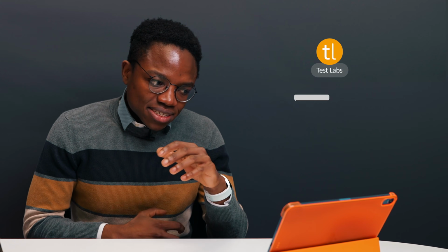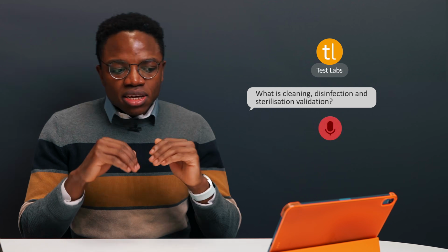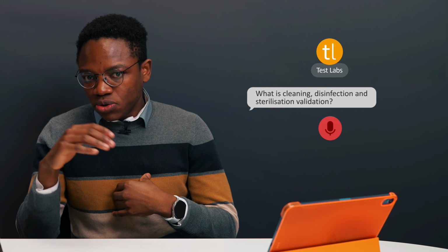The next question I get quite a lot from manufacturers who don't have as much experience within the setting as a whole. What is cleaning, disinfection, and sterilization validation? So essentially, when you term your medical device as reusable, it needs to go through reprocessing before it's fit for reuse on another patient, for example. Part of that reprocessing includes a cleaning process, a disinfection process, and a sterilization process. Cleaning and disinfection, at least in the UK and Europe, are typically done in a device called a washer disinfector. And this is specifically designed to clean and disinfect medical devices to a very high grade, so we can all be assured the sort of patient that these are getting used on remains safe, right?